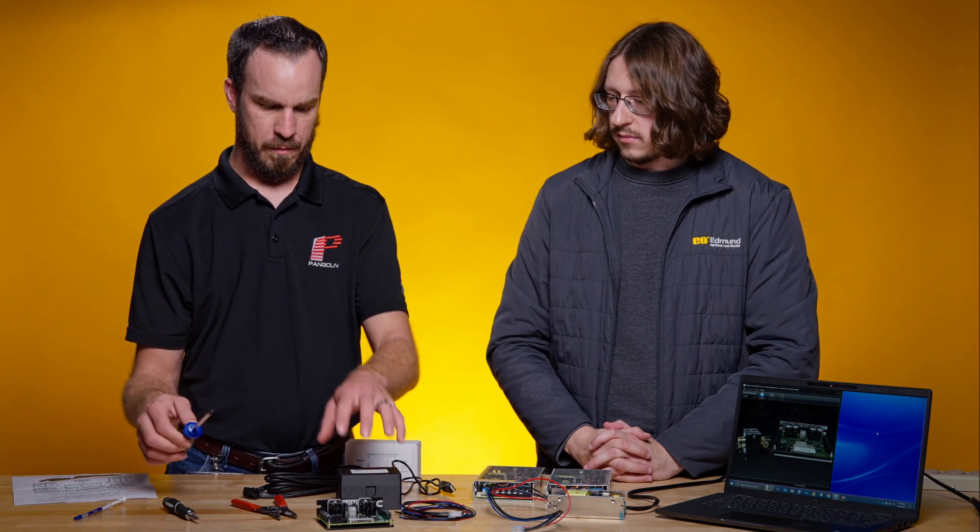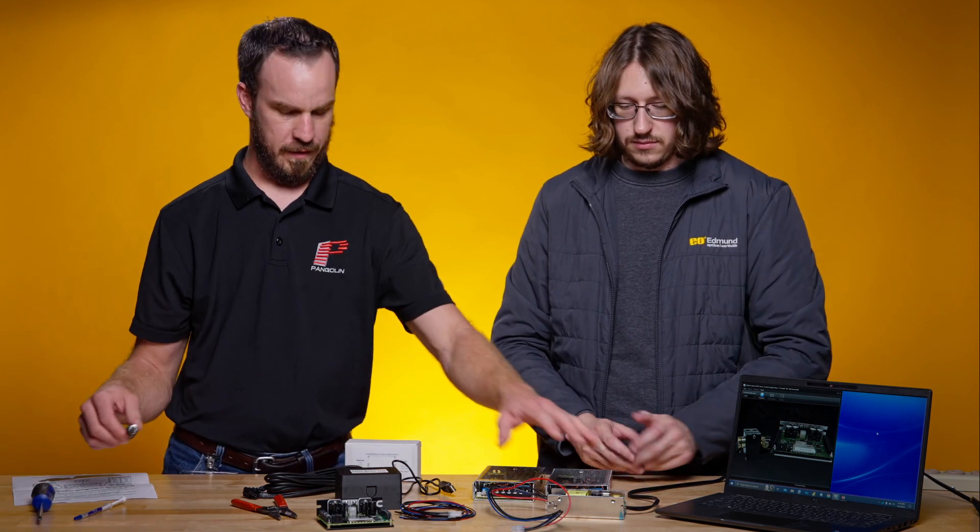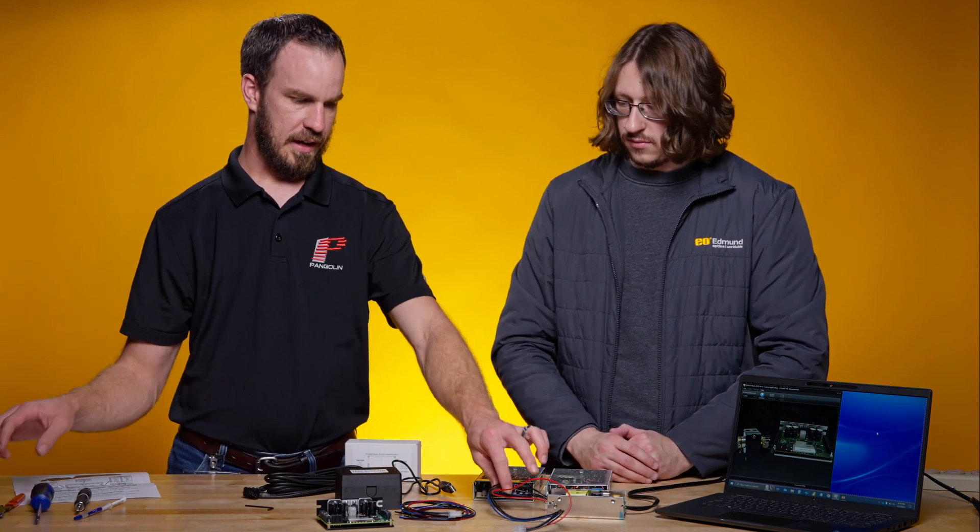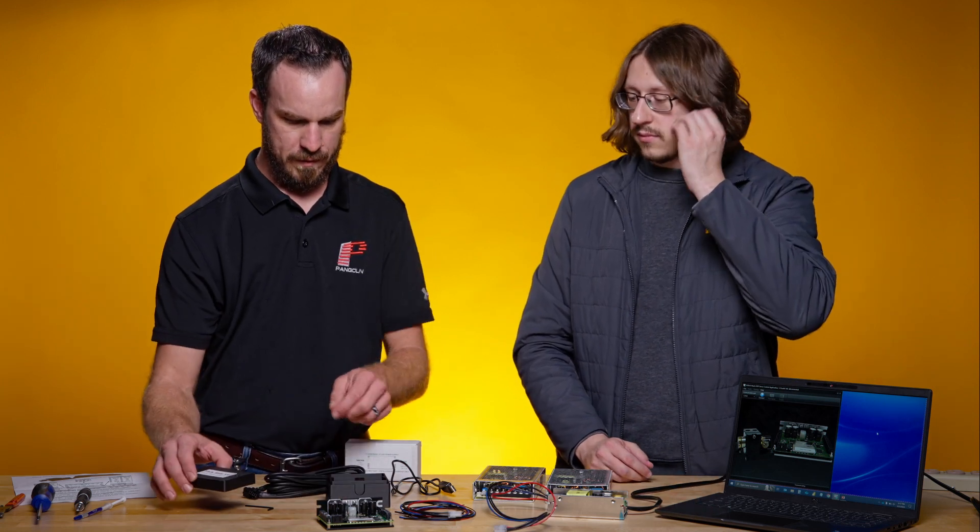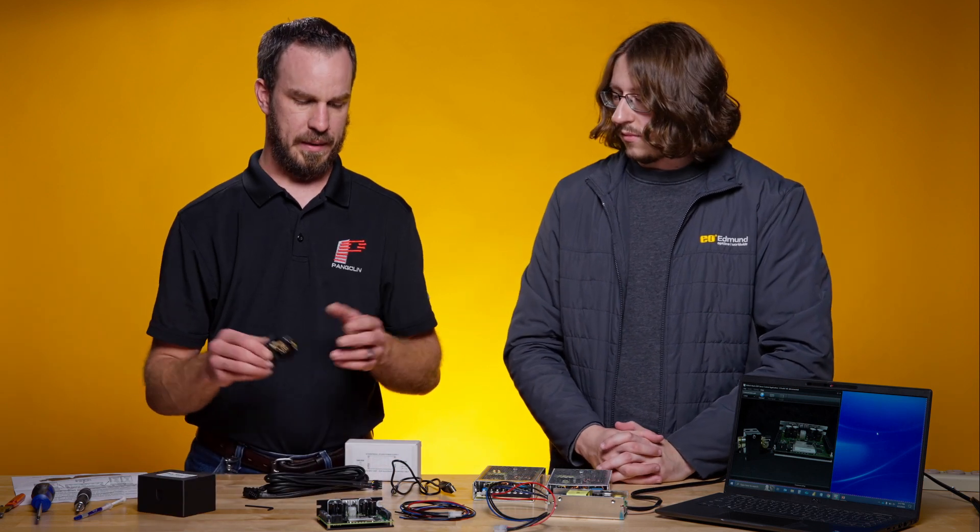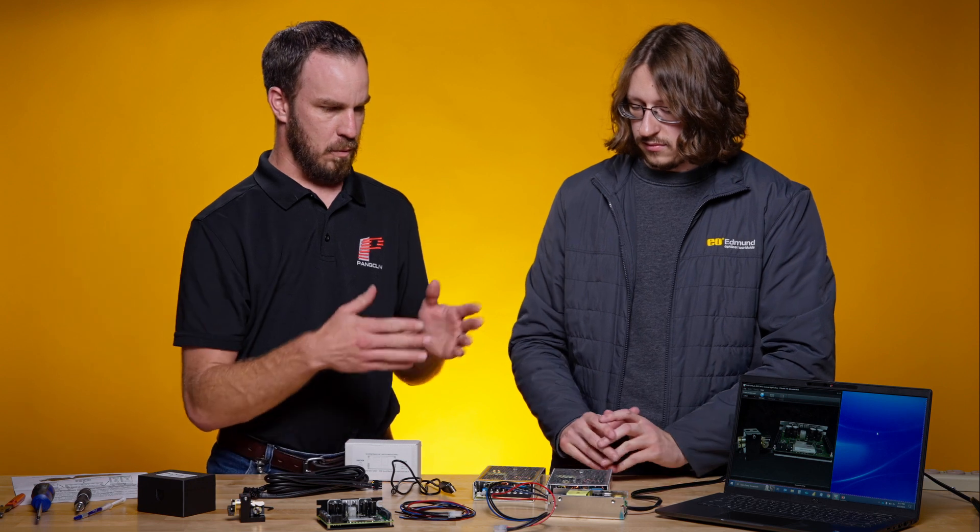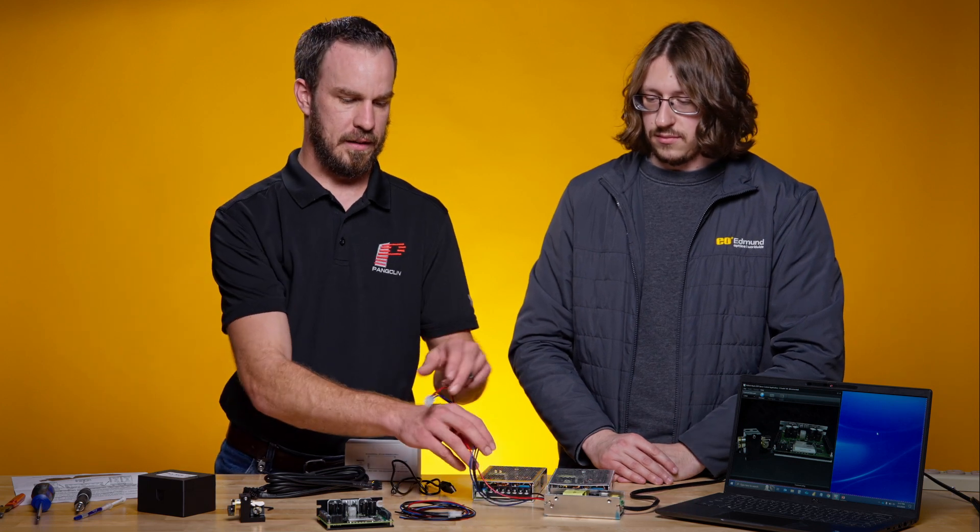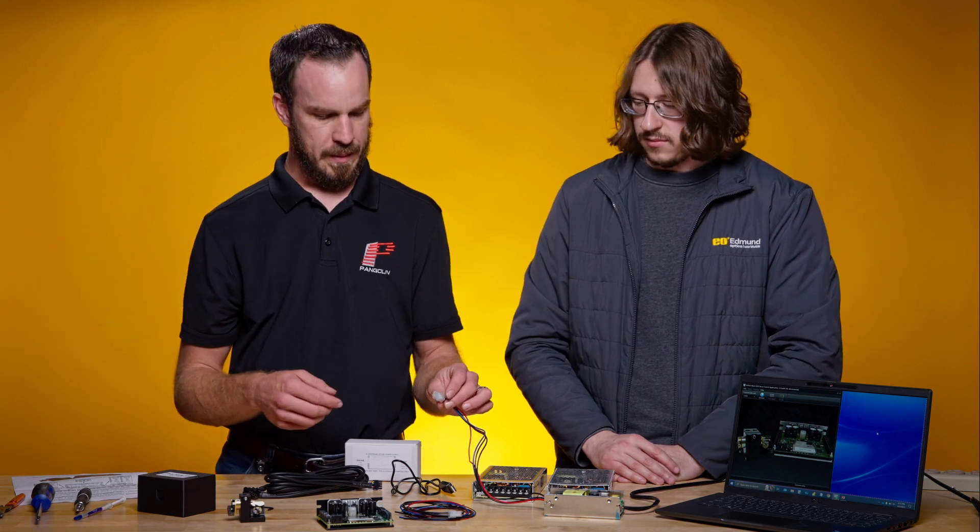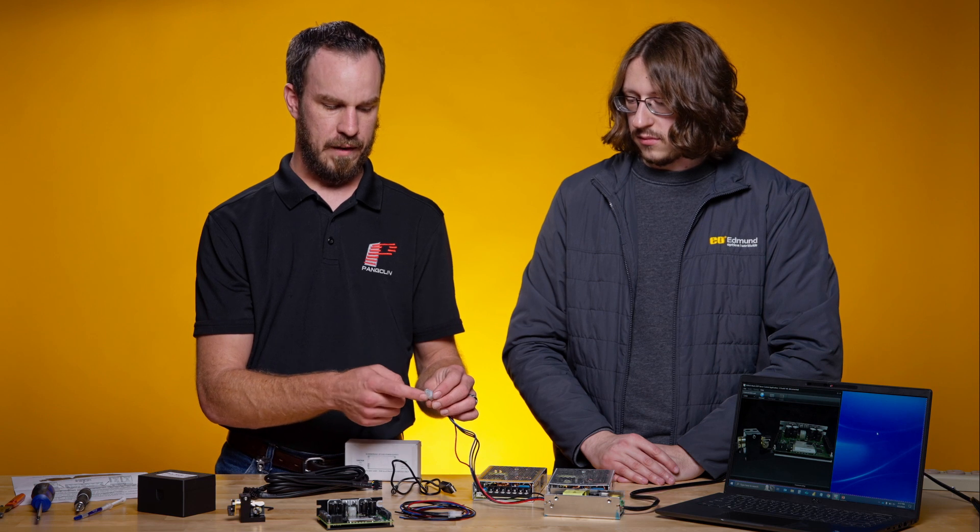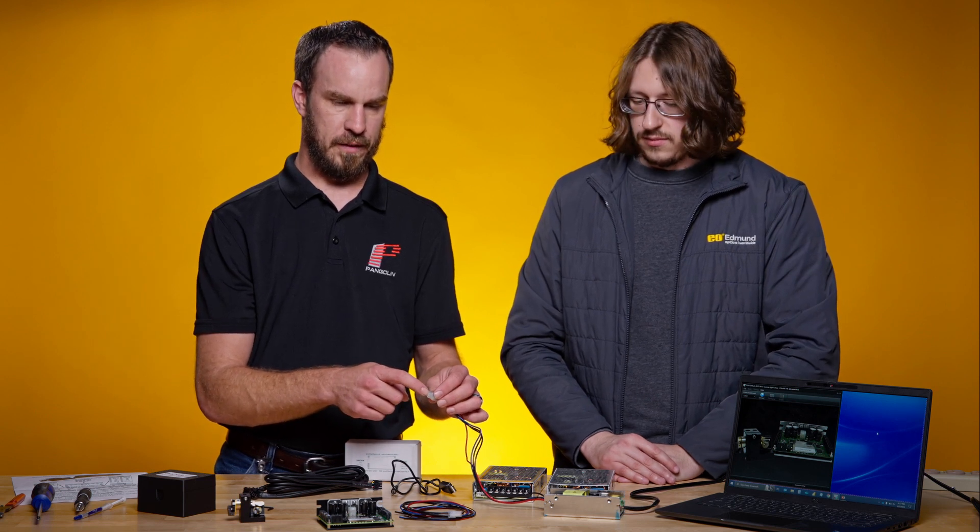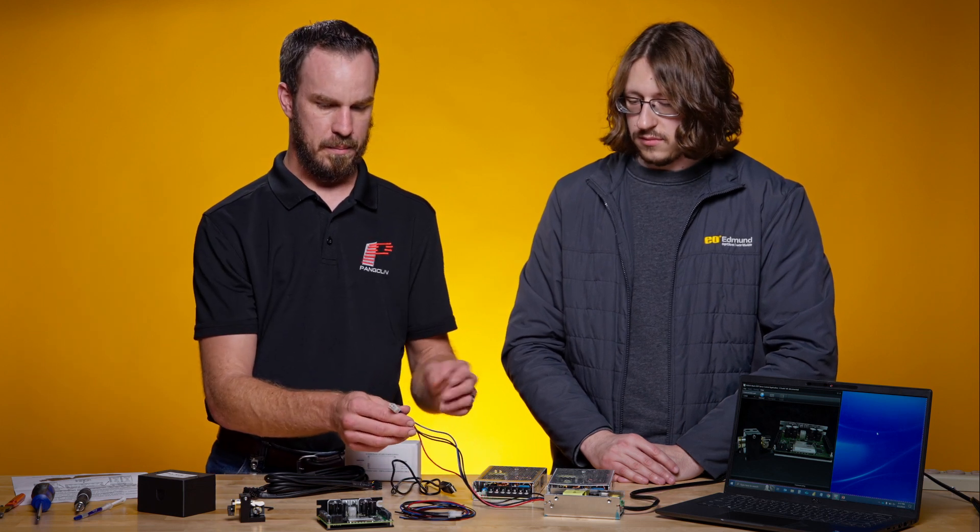It's pretty simple to set up. The only external tools you should need are a small Phillips screwdriver for removing the galvos from the box, small flathead screwdriver for the power connections, and then a wire stripper to make your analog and your power supply connections. We've got the galvos that come in the box here. When you go ahead and start making these connections, we recommend once you've got your power supply wired up before connecting it to the Mach DSP, please verify your connections are correct. You can do this with a voltmeter, which is also not included with the system, but most labs have these. Please make sure you have plus 24 volts with reference to ground on the red wire and minus 24 volts with reference to ground on the blue wire.